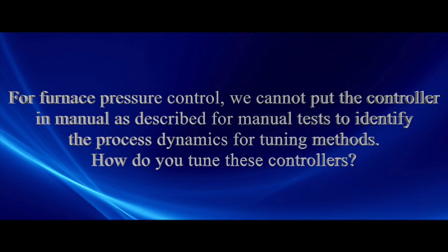Yeah, we've done that. There's some, and that process can, and I've been in others that can ramp off scale in a second or two. You can't put it in manual. There's some thought that we could make a setpoint change and maybe figure it out from that, but what has worked is what I briefly described.